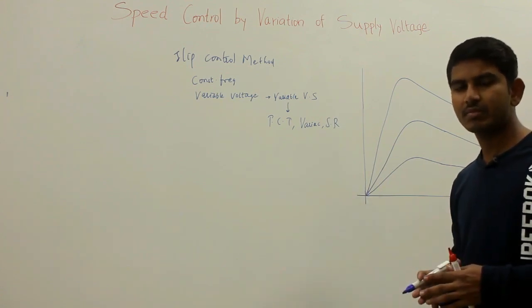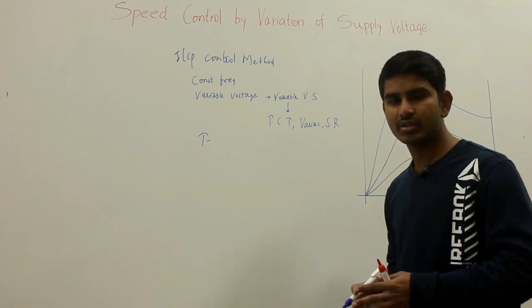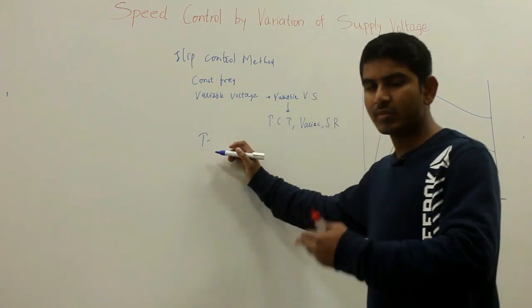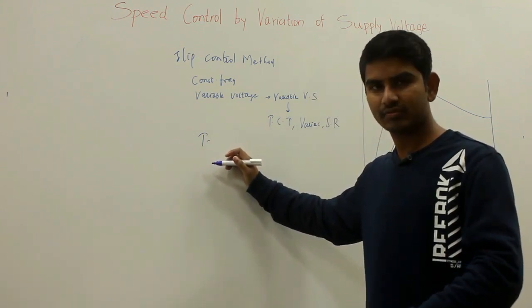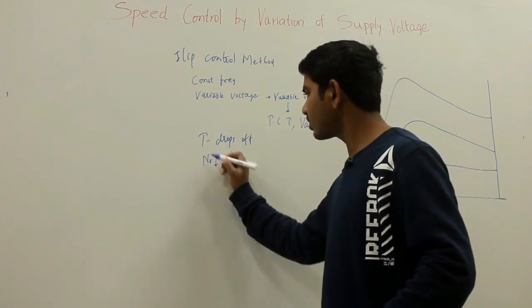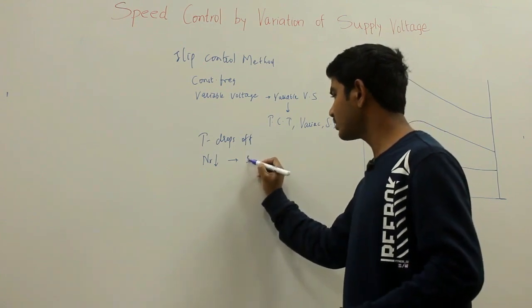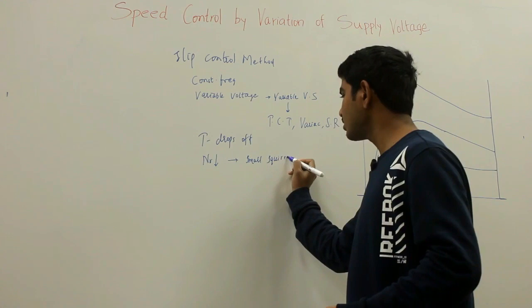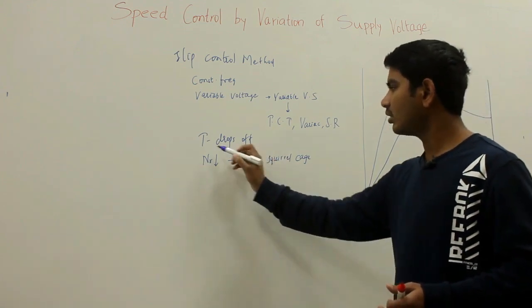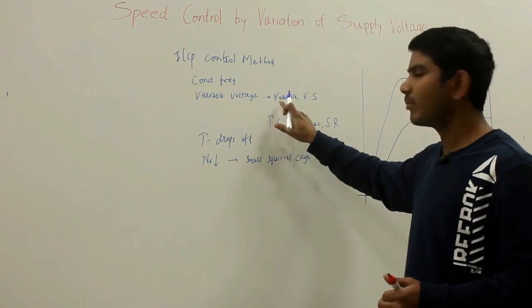Due to those limitations, this method of speed control is used only for loads where the torque required drops off considerably as the speed is reduced. Such characteristics can be found in small squirrel cage motors driving fan loads. Here we can obtain a variable speed by supplying variable voltages.